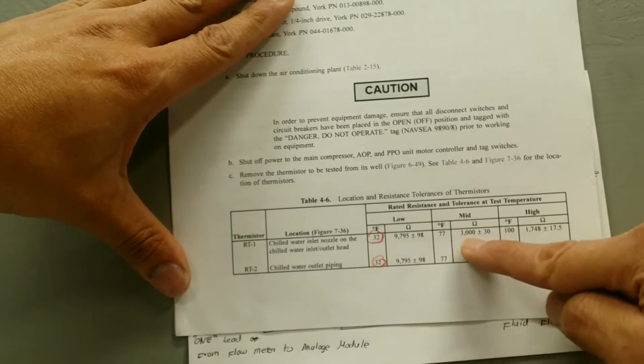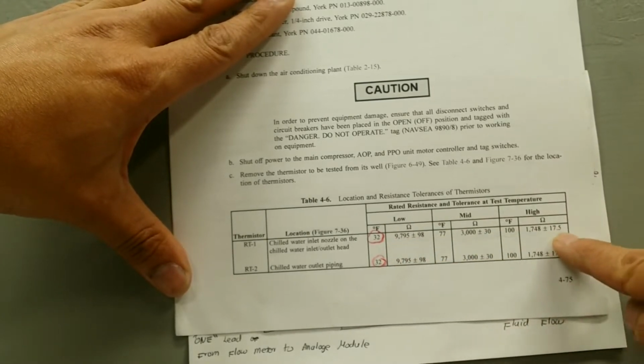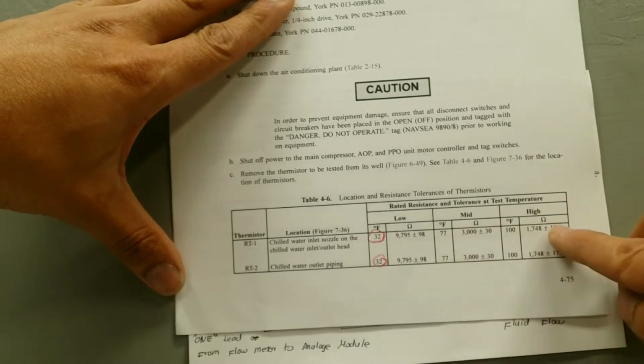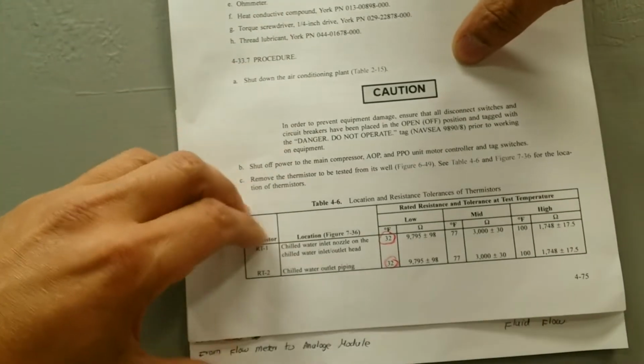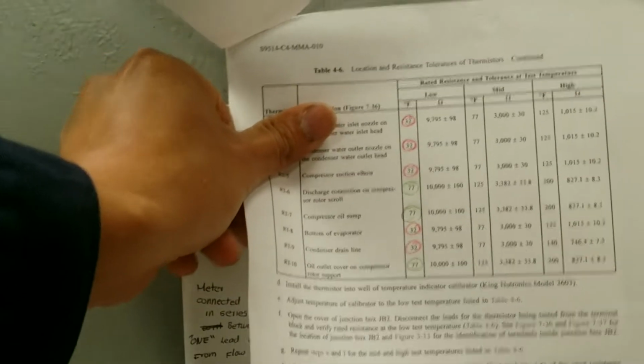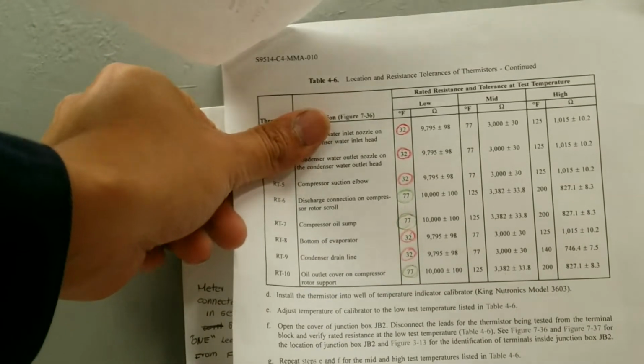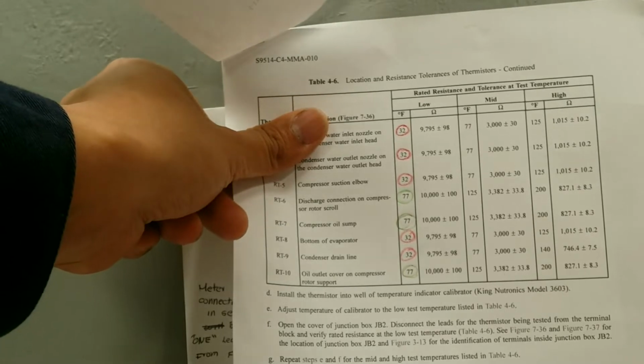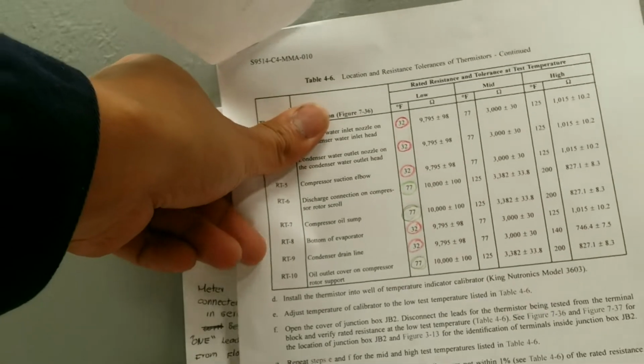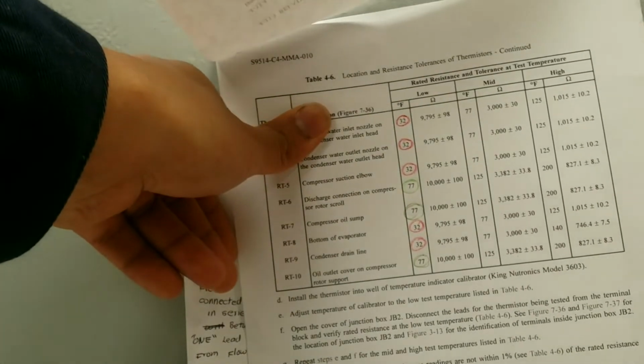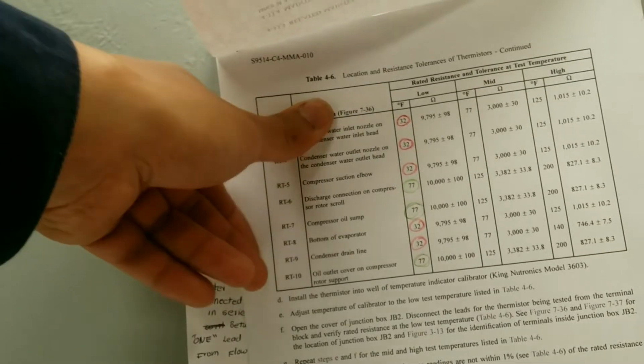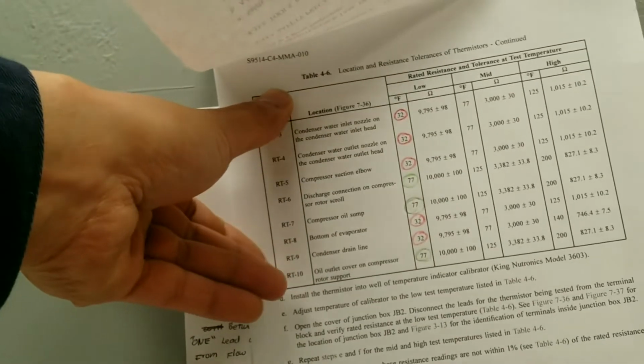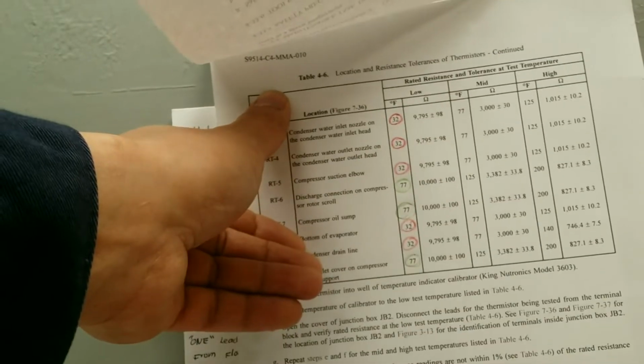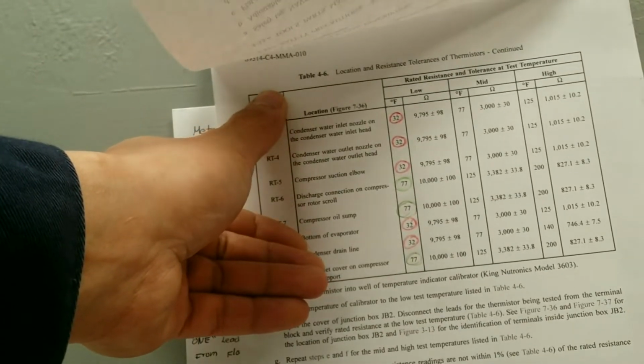At 77, it will be this much. So that will give you a good high, a good medium, and a good low. And it is listed for all 10 of them, as you can see over there. I like that because you don't even have to take it from the system to test it, although it would be best to take it out of the system and have the gauge calibration guys put it in their temperature machine so that you can actually verify that they are working right.